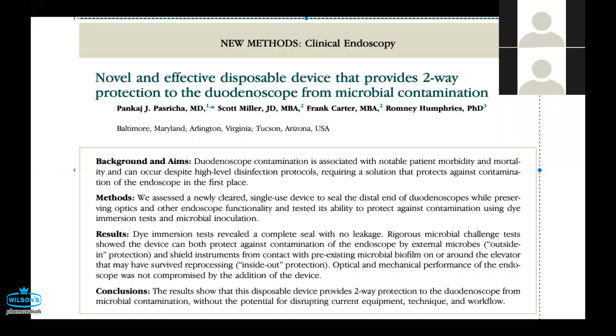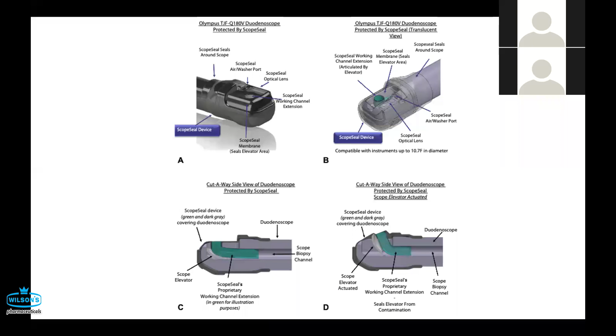It does not increase the cost to the same level as others. The price of this is not fixed as yet. It is still not available for regular use, but this study, done elegantly, has looked at a number of things. It has looked at whether applying this seal compromises the quality of the endoscopy and your images. It has shown that there is no leakage. It shows there is no collection of microorganisms, and so the disposable device provides two-way protection to the duodenoscope from microbial contamination without the potential for disrupting current equipment, technique, and workflow. So quite promising, but I think it has to be validated by different centers, and the price has to be competitive or affordable so that it doesn't add much.